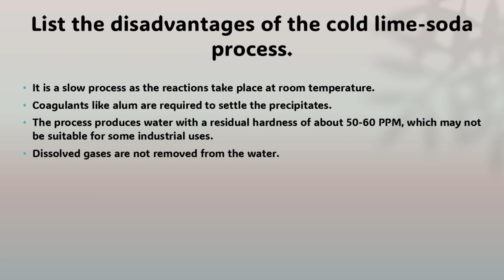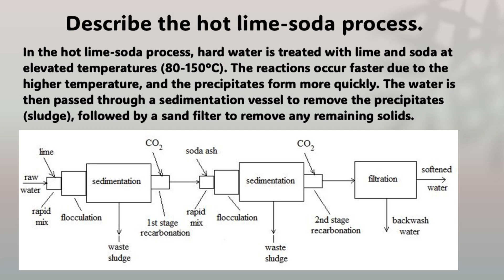The next question is: question number 34. Describe the hot lime soda process. The answer to this question is: in the hot lime soda process, hard water is treated with lime and soda at elevated temperatures, 80 to 150 degrees Celsius. The reactions occur faster due to the higher temperature, and the precipitates form more quickly. The water is then passed through a sedimentation vessel to remove the precipitates (sludge), followed by a sand filter to remove any remaining solids.